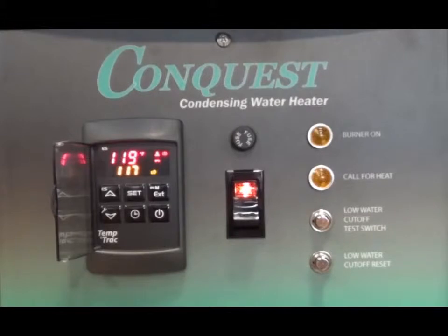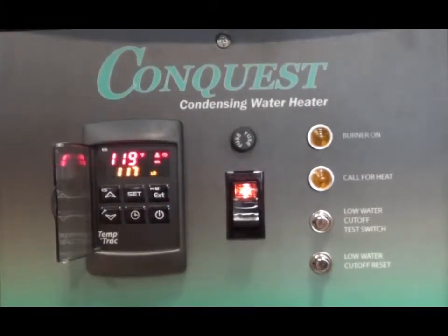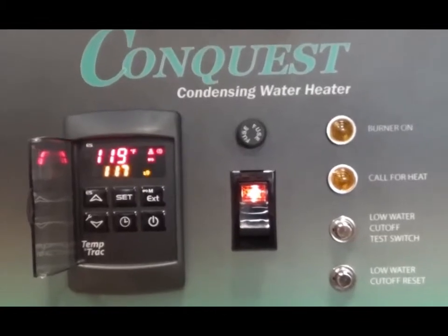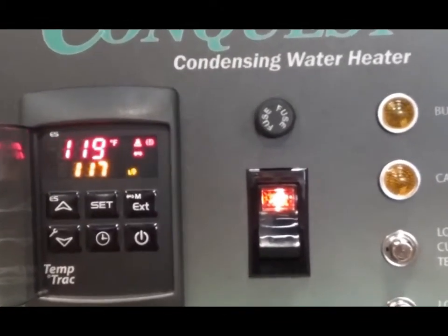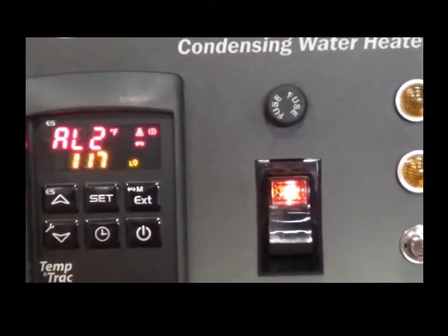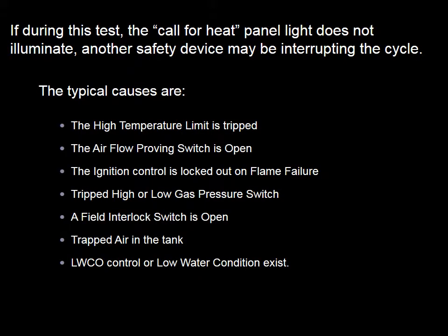After a brief delay, the Temptrac control will sense that ignition did not occur and will shut down, emit an audible alarm, and an AL2 alarm code will flash in the upper display. To silence the alarm, press any button on the Temptrac control. To reset the lockout condition on the ignition control, cycle the main power switch off and then on.